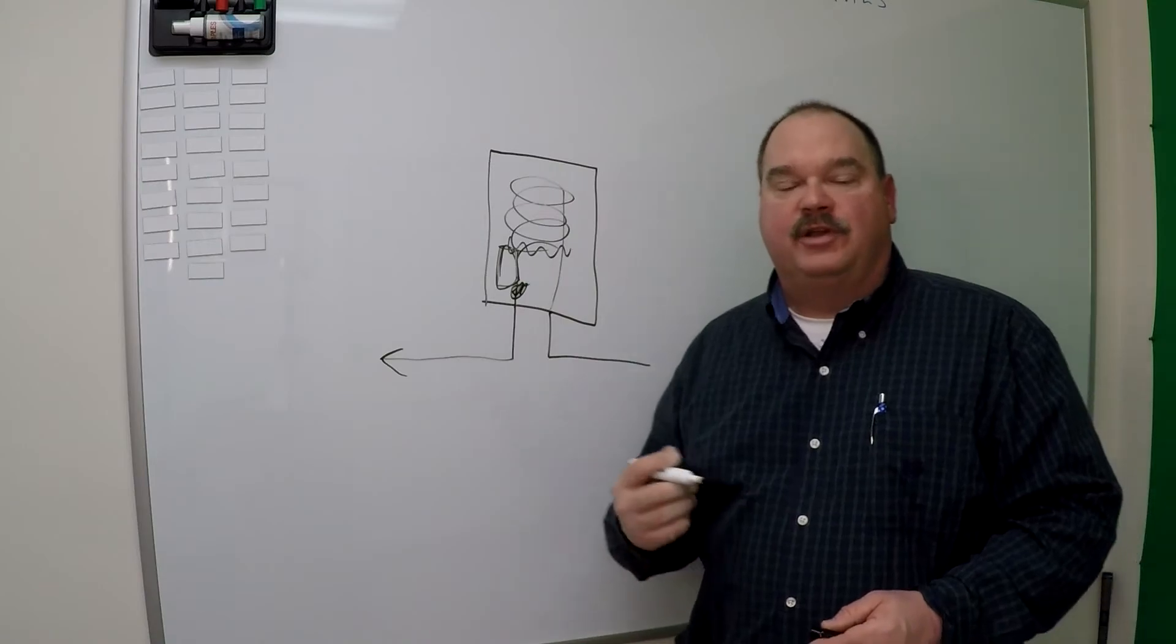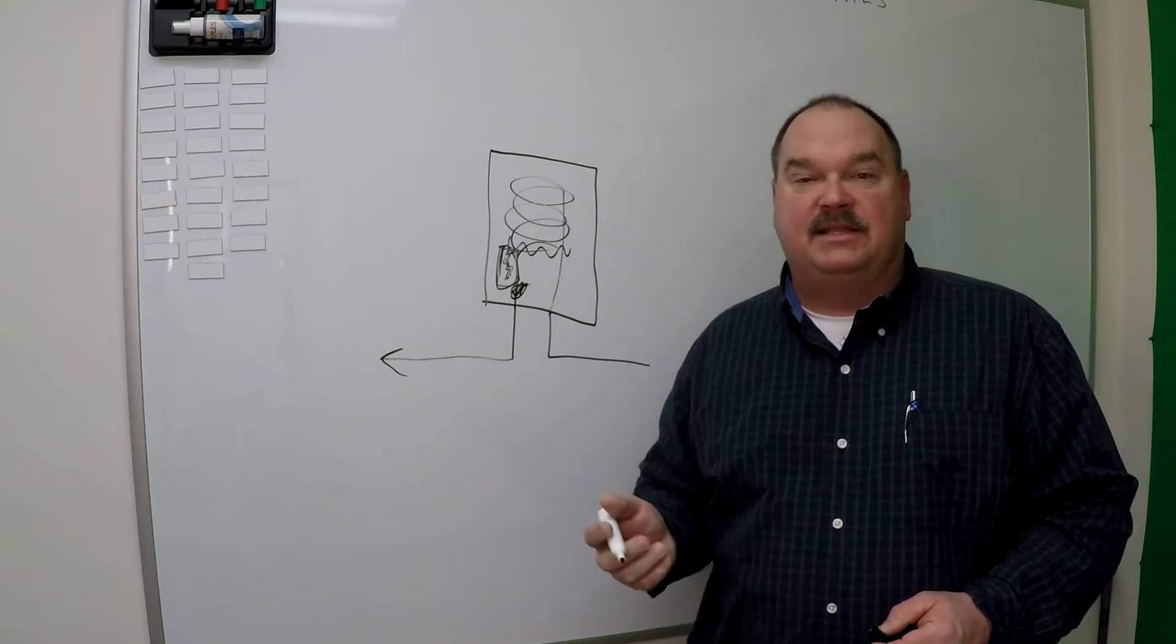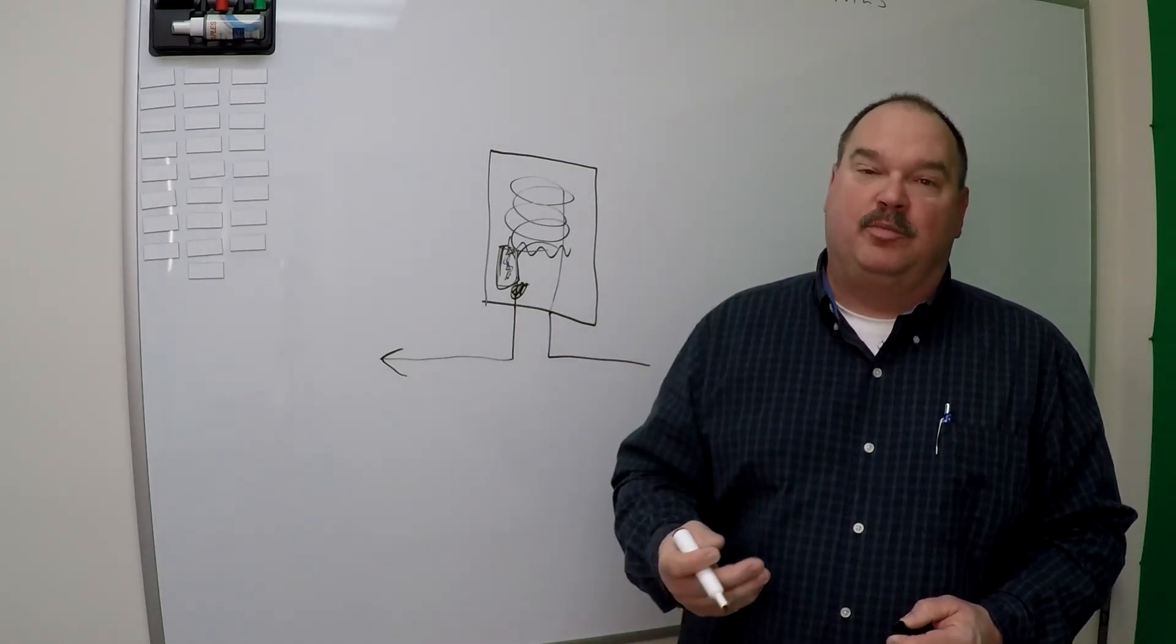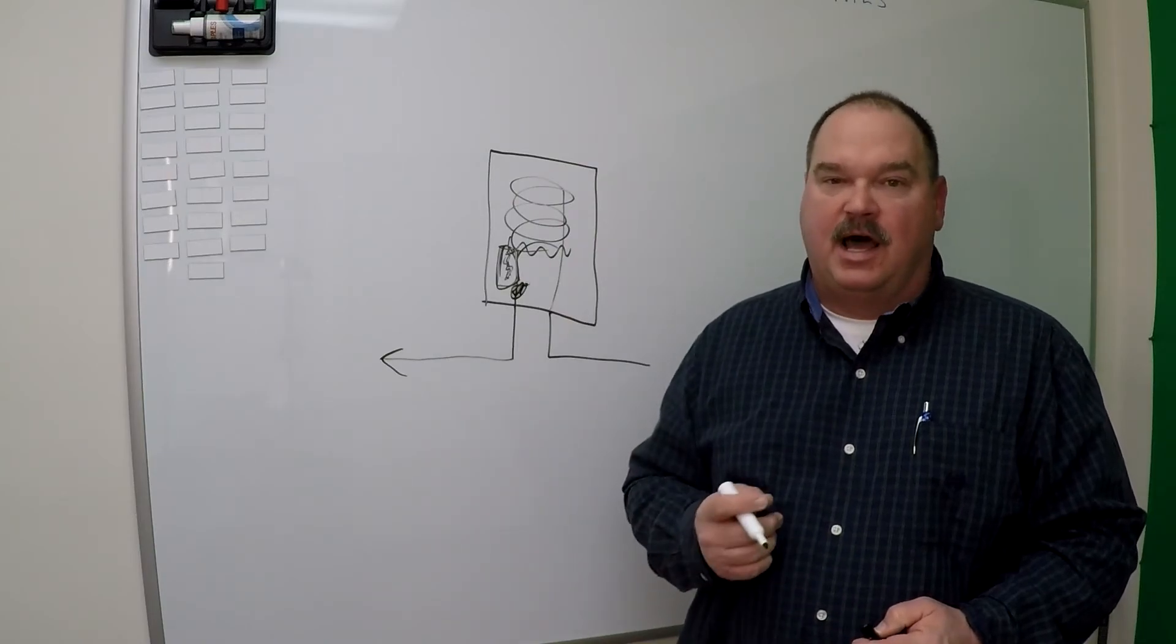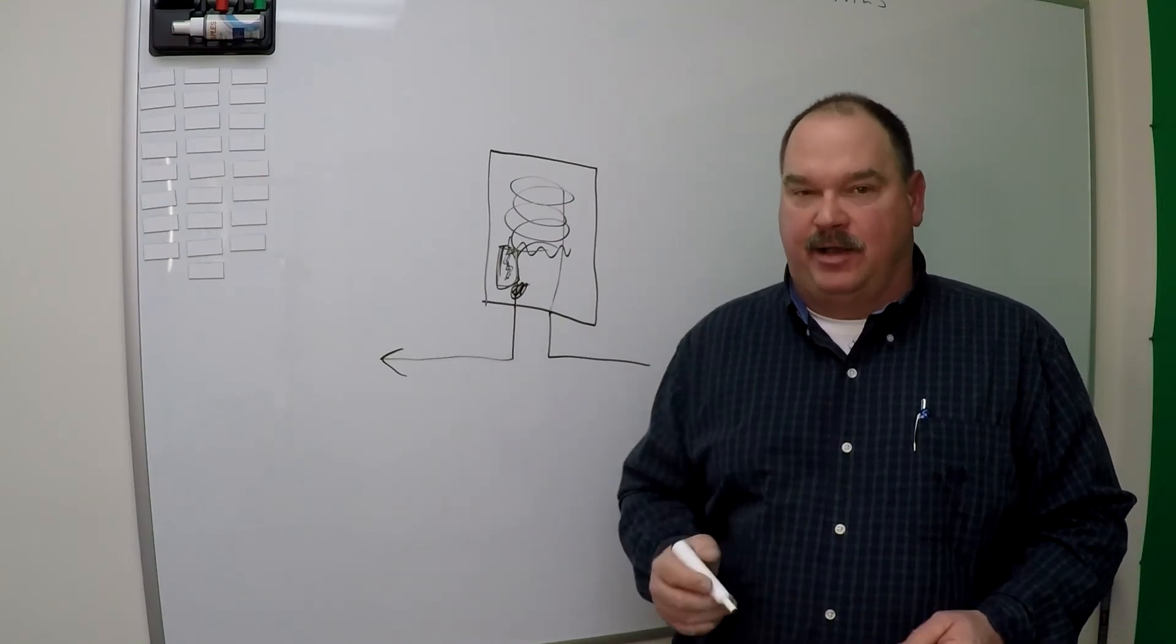There's also an onboard circulator pump and controls, and you can set it up for internal circulation, which will keep this little tiny thermos bottle hot, which means there is no wait time for that heater to fire up, and there is no minimum flow rate for you to start getting hot water. Even a trickle of water will deliver hot water from a Navien NPEA model.